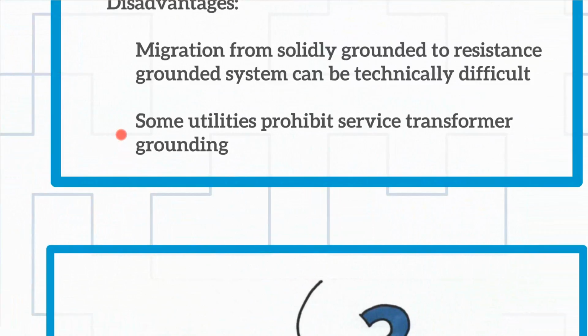And what I have done is I've been hired many times through my career by the industrial or end user to go fight with the utility. They'll have a lot of transformers for the utility, like Delta 69 kV, for example, to 13.2 or 15 kV class, and it'll be solidly grounded on the secondary. And if I get a ground fault on the secondary between the transformer and the service entrance to the switchgear, that ground fault is going to be single phase, it's going to be big amps, and it's going to reflect through the transformer times 1 over the square root of 3 and look like a phase-to-phase fault, and it may take 10 seconds before it clears.